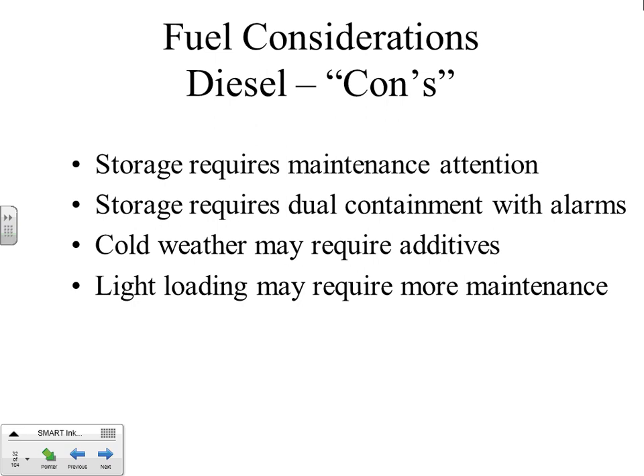And there was black juice dribbling all the way down the side of the block. What that was, it's unburned fuel. Same with light loading. The diesel is designed to run under load, and the temperature is directly proportional to the amount of load that's on the set. So if you don't get that engine up to temperature, they don't have gaskets like a gas engine does.